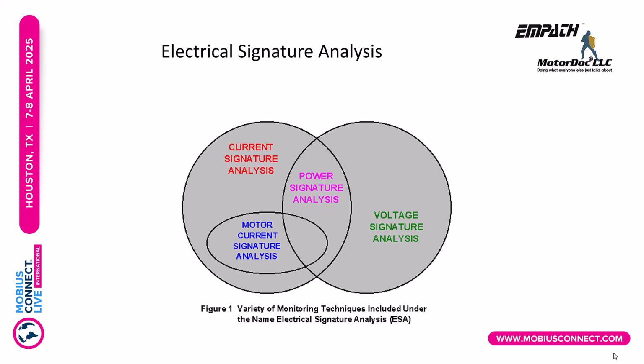But I'll tell you now, based upon the cost of the instruments in the field, if you're using it for rotor testing, you're wasting your money, basically, because I could tell you about a rotor bar condition with an inexpensive analog clamp-on ammeter. In reality, the way Howard Haynes had seen it was you have voltage, you have current, you have power quality, you have the ability to see electrical and mechanical components. In particular, the discovery for ESA was not what has been claimed in the past in some marketing articles. It was really to look at the bearings and gears and related wear in both of those in motor-operated valves for the nuclear power industry.